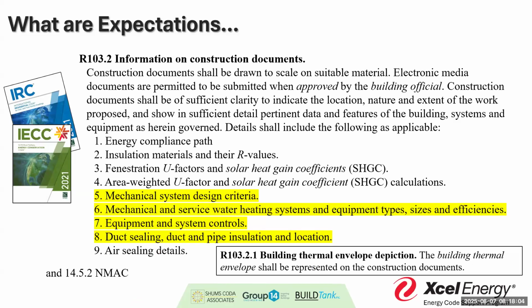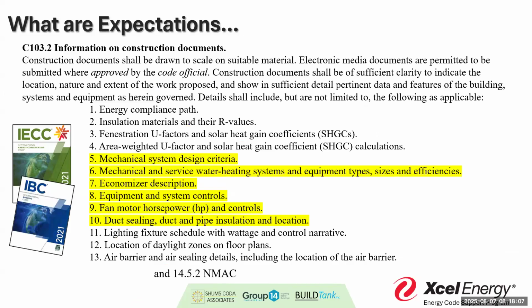But this is what we're thinking about when we talk about energy compliance. What we want to know, between residential and commercial, is what is the design? Show me, please tell me you've calculated which piece of mechanical equipment is supposed to be in this building. Because too often we'll find, no, we didn't - this is just the last thing we did, and this is the one we bought. So you want to know those pieces of equipment, their efficiency, their types, their fuel systems, their ventilation, their fan systems. What are the ventilation requirements? How are we going to get this moving around? What does that duct look like? How are we transmitting this conditioned air around the building?